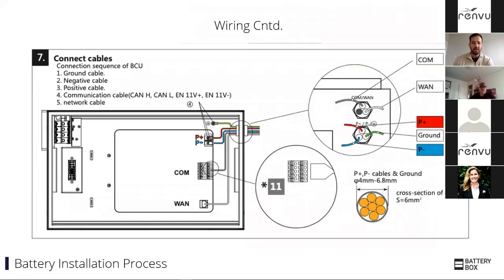Getting into the wiring, at a high level, you're wiring the battery to the inverter. The battery always sits behind the inverter. The inverter makes the decisions about charging, discharging, and what's going on in the home because it has visibility that the battery doesn't have. All the battery does is communicate its state of charge to the inverter, and the compatibility is worked out so the inverter knows what to do. Of course, the battery can protect itself in case of malfunction — it has breakers and relays inside. But for the most part, it just reports its status, and the inverter makes the charging and discharging decisions.